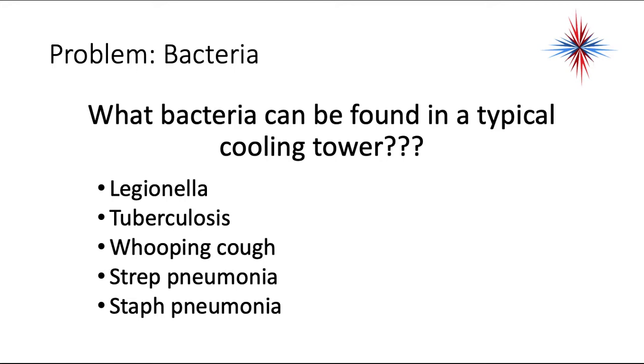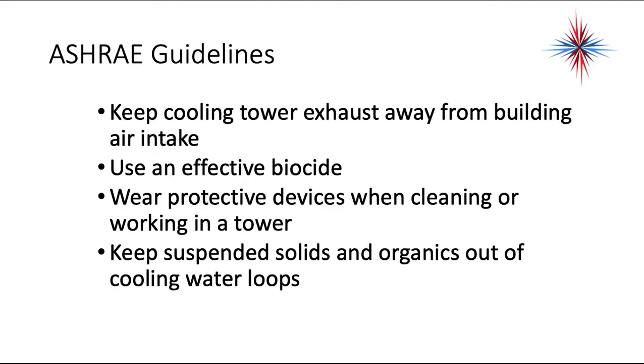It has been confirmed that these problems can be associated with the same source: building cooling towers. The problem is recognized by ASHRAE, which has published guidelines for controlling problems in cooling towers. We have to keep cooling tower exhaust away from the building air intake. We want to use effective biocides to treat the water. Technicians should wear protective devices when cleaning or working in a tower, and we want to keep suspended solids and organics out of cooling water loops.